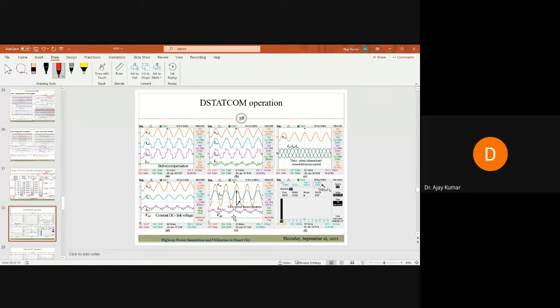You can observe from this first diagram: this is your load current at the third channel, and this is your source current. Initially, before applying any control algorithm, both source and load current have similar shape, and no compensating current is given. After applying the control algorithm, your source current becomes completely sinusoidal. This is your load current, and this is your compensating current, which compensates the load current so that the source current becomes pure sinusoidal.